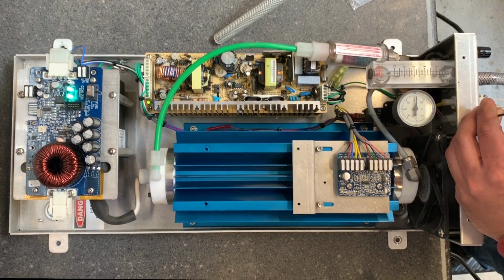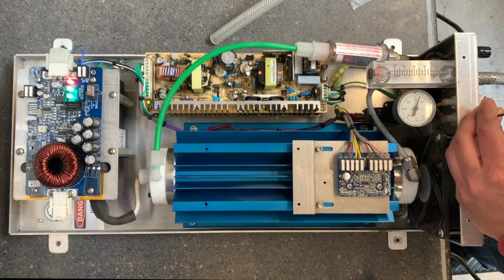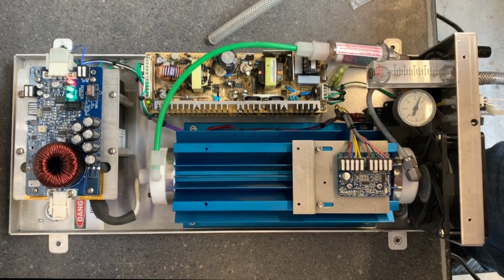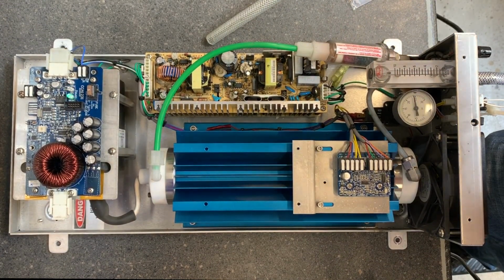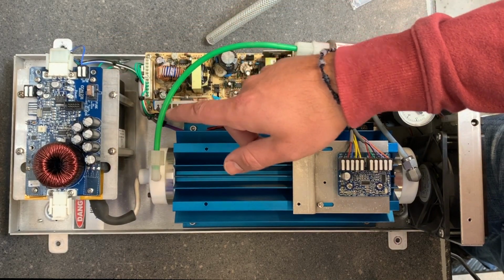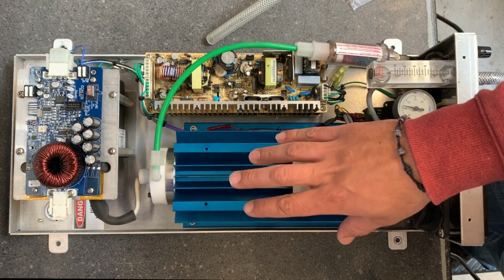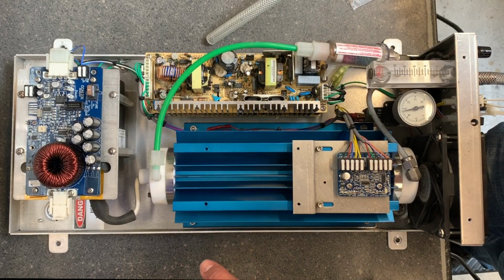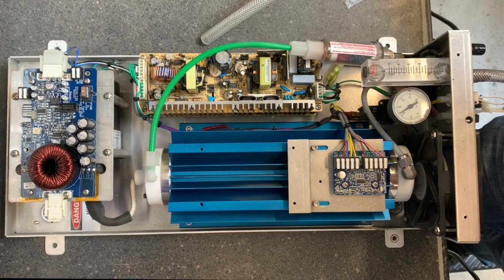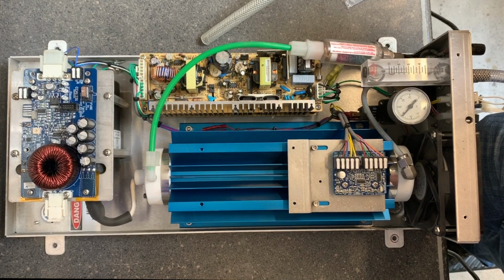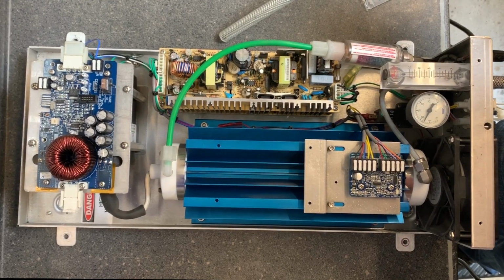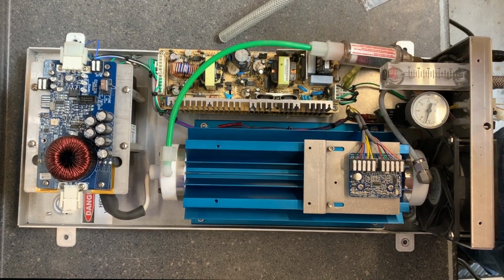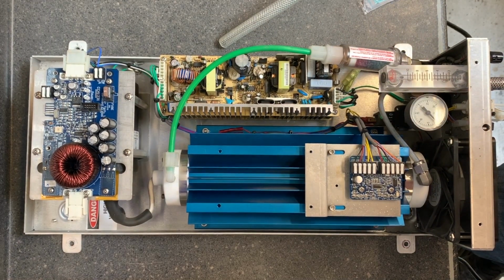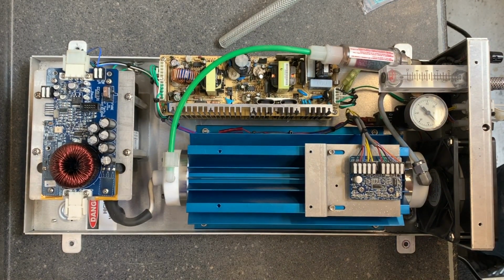So once you let it start ramping up, once it tries to hit 100, if you get that red fault light, there's usually 3 things that are wrong with it. It's going to be a bad drive board, a bad transformer, or you have broken glass in your chamber, or it's arcing somewhere here. So I'll show you how to check to see what is going on with it. First I'm going to show you how to check if your transformer has gone bad.